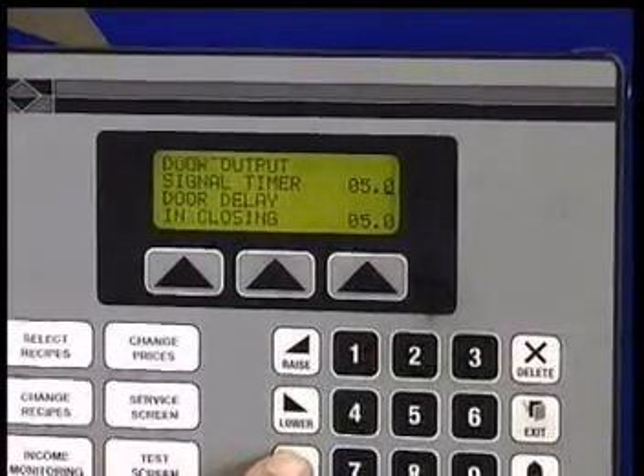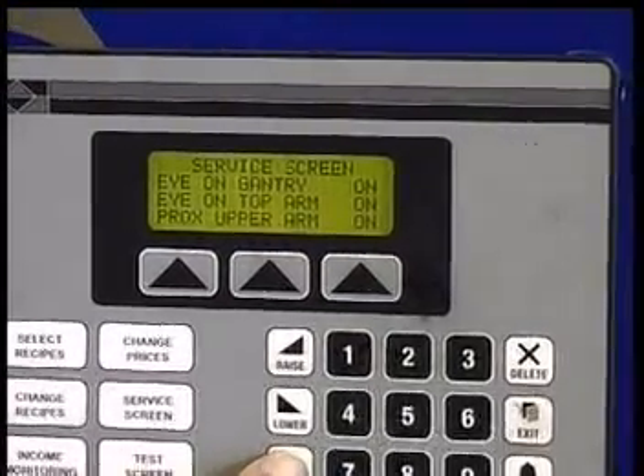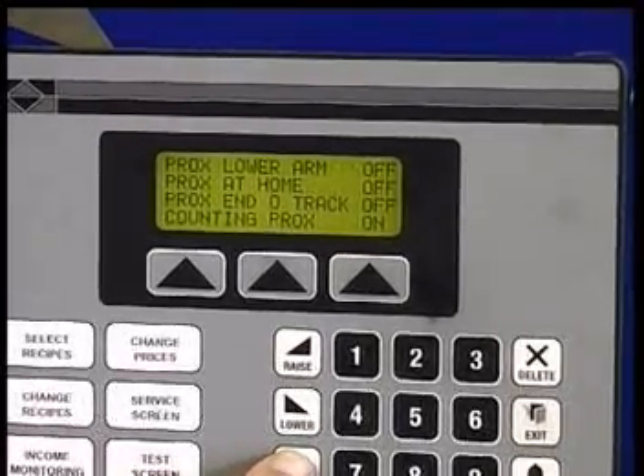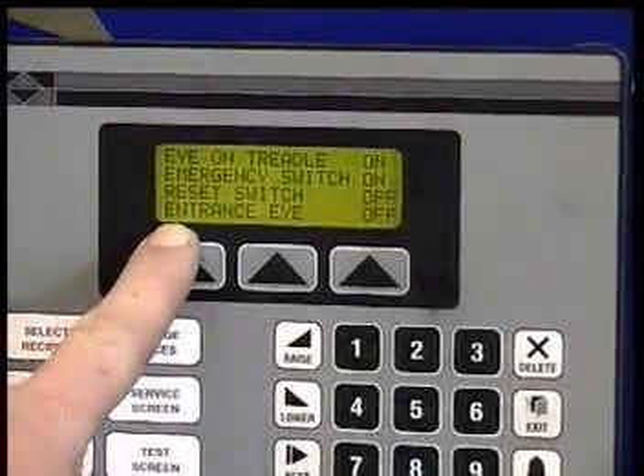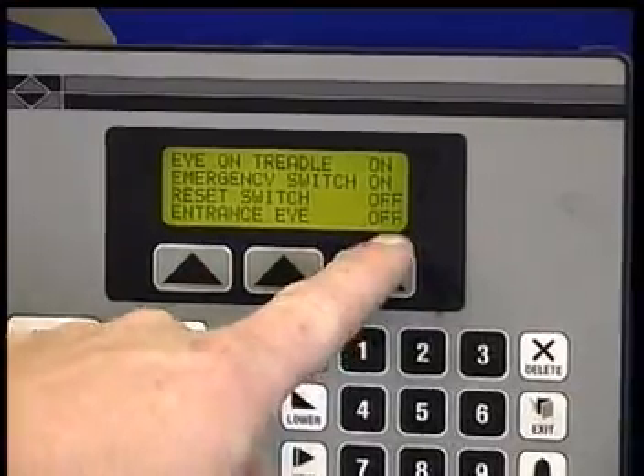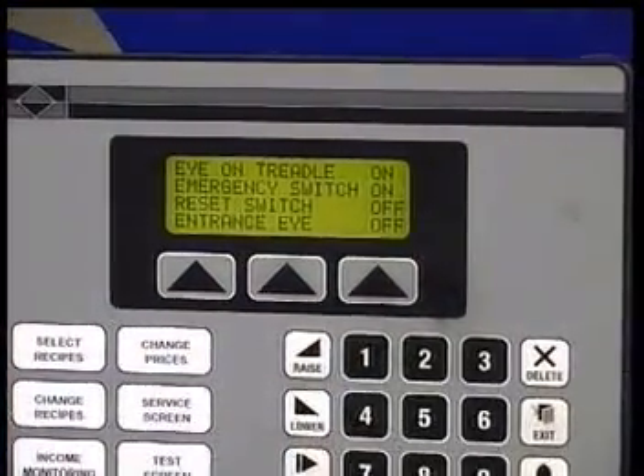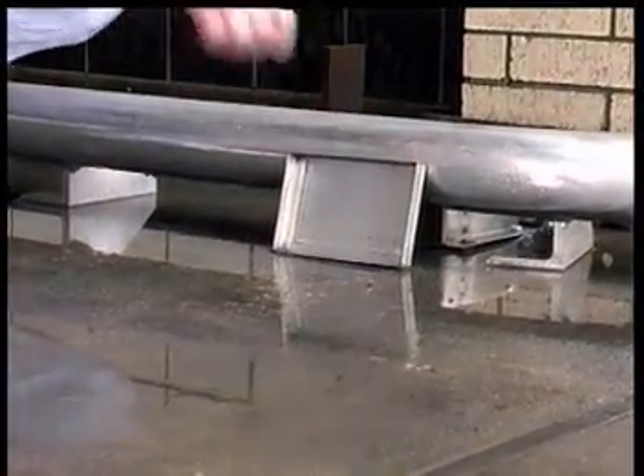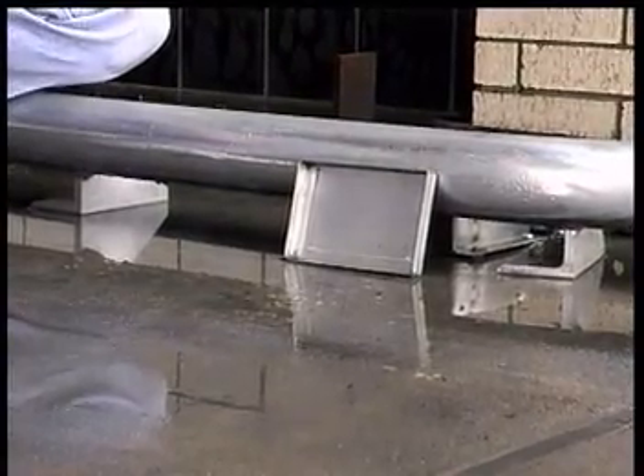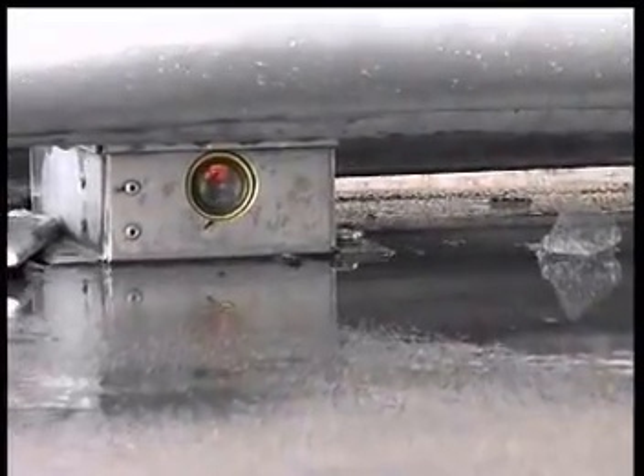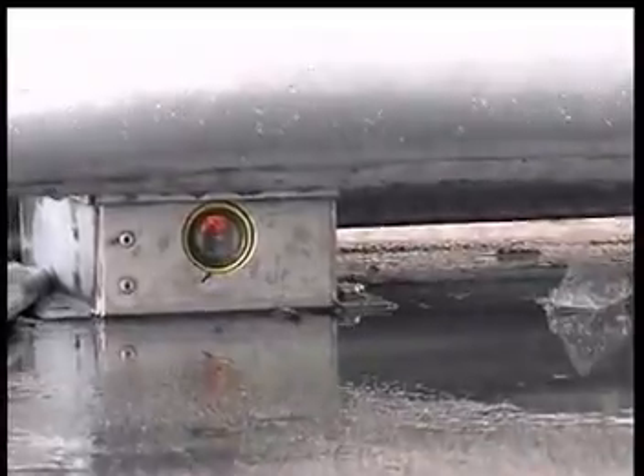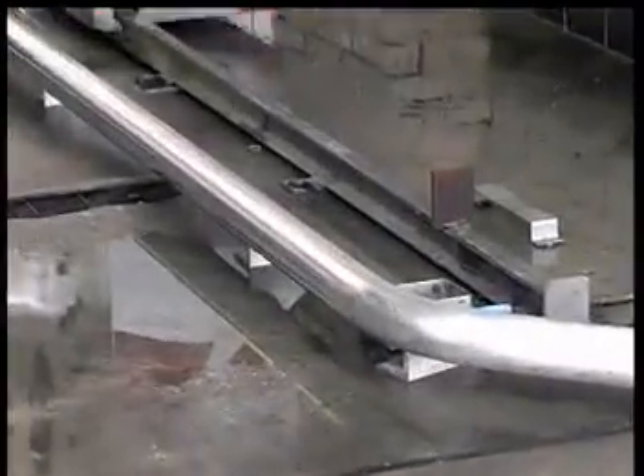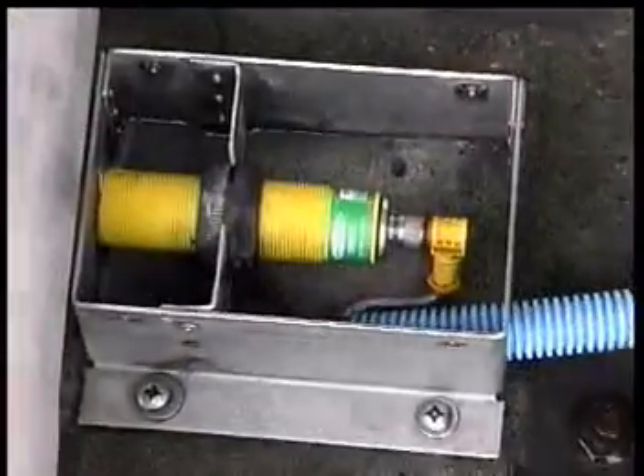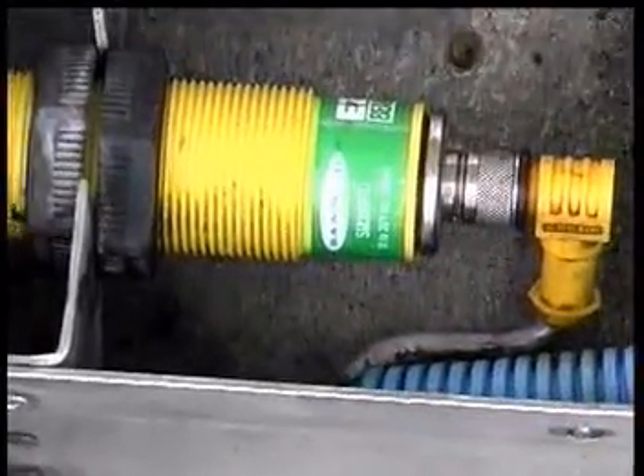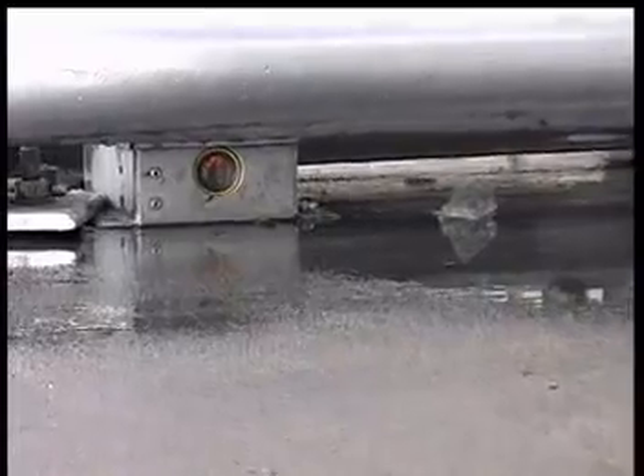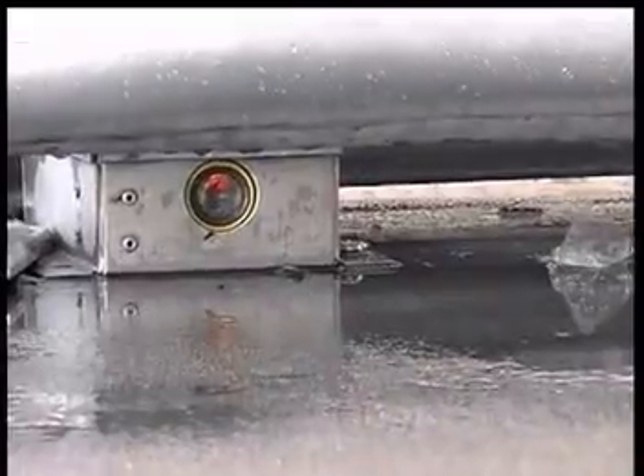Using the service screen, determine the normal at-home and no vehicle in the bay status before checking operation of the banner eyes. You'll find them listed in the manual under the Operator Interface Panel tab. To change the status, block the eye and check the service screen. If it does not change, check for a red light on the transmitter eye. The transmitter's model number is labeled with EQ and is located on the passenger side of the wash bay and the gantry. The red light indicates that there is power on the transmitter.